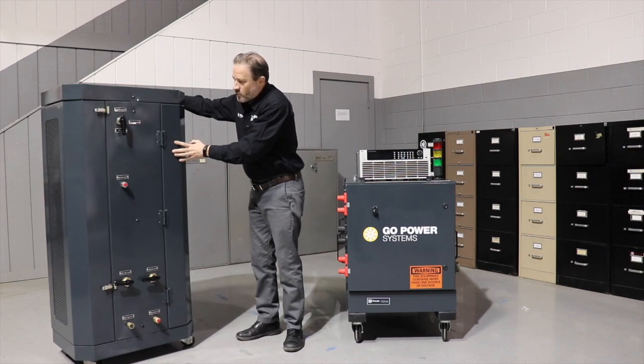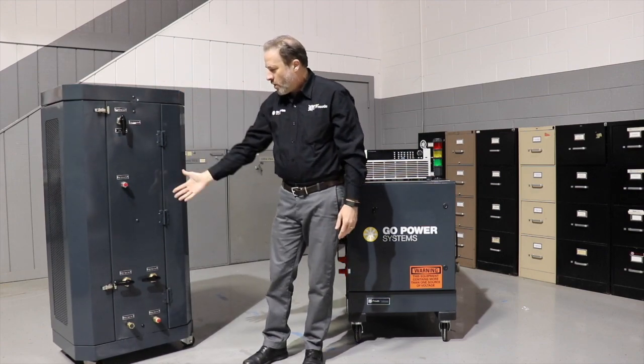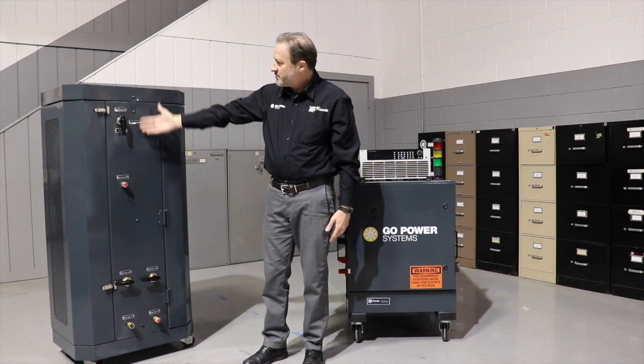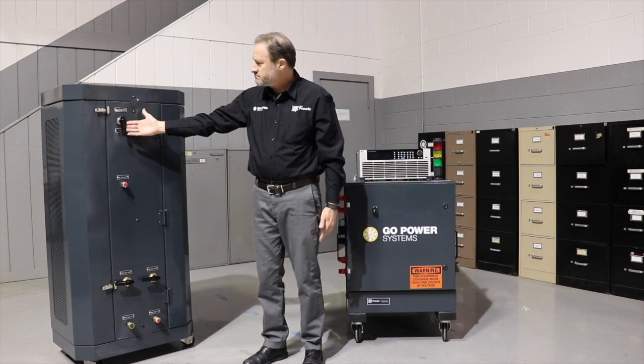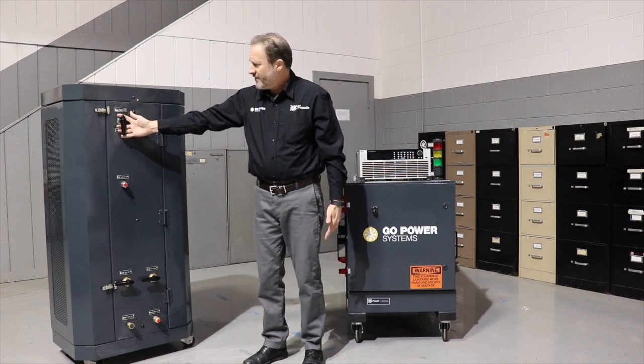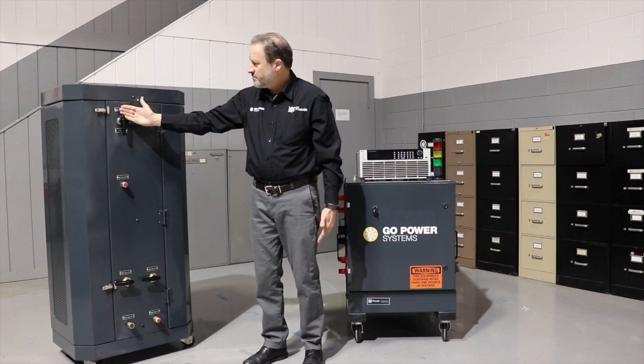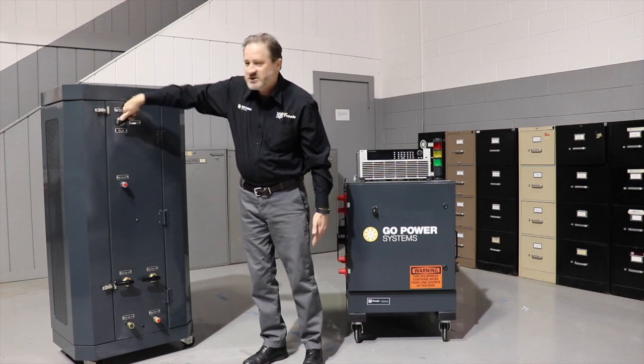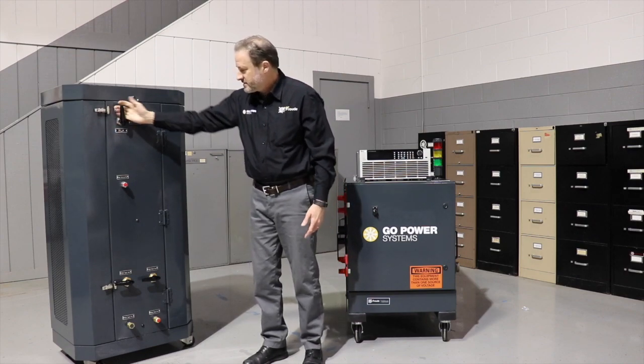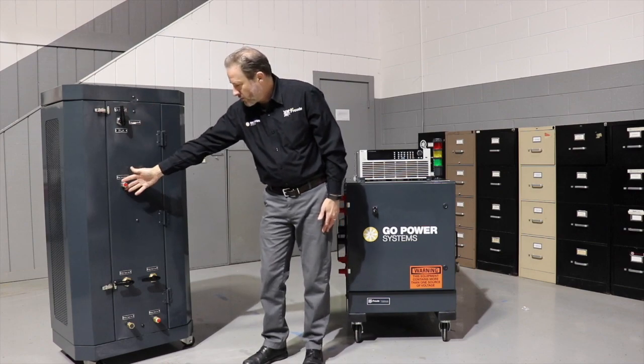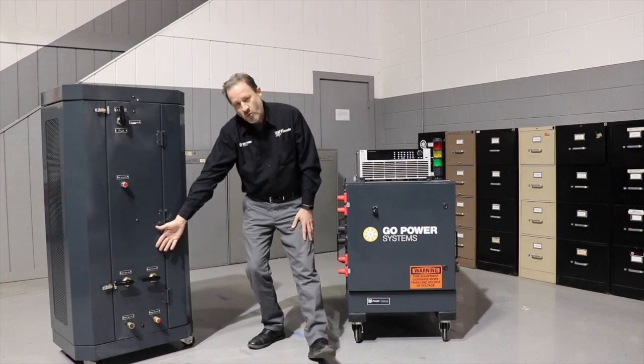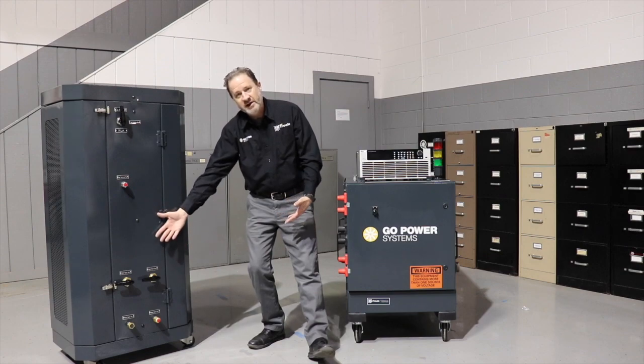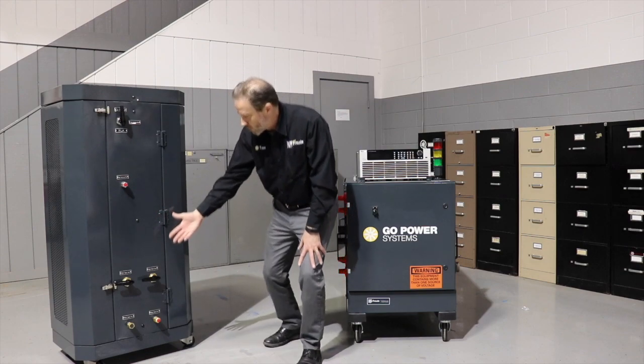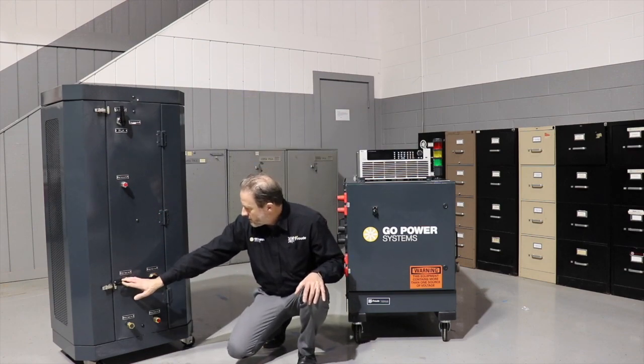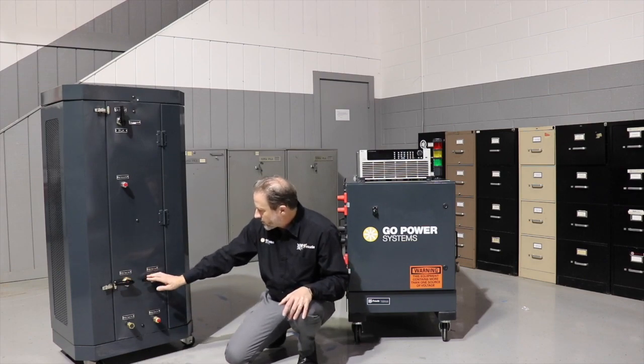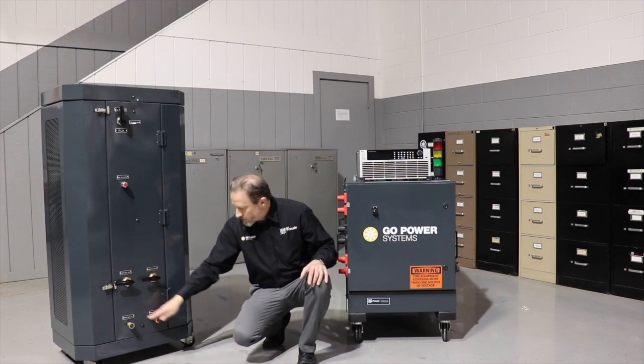On the other side, we have our water and calibration side. From top to bottom, we've got our calibration valve - you put it in calibration mode to calibrate, or the run position to actually run the device. Below is our calibration port. Further down is where our water facilities come in for our heat exchangers, cooling the fluid or fuel. So you have supply valves and water return valves, and below those, the corresponding ports as well.